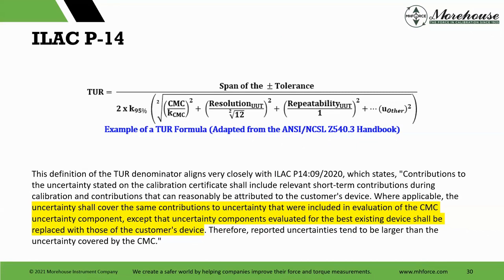So what we've done is we've simplified it down to, hey, we're making an assumption that people have done the CMCs correctly, and then we're saying, hey, what if we're going with ILAC? If we're accredited, we have to go with ILAC P14. So how do we make this formula work for ILAC P14? We say, okay, there it is. Uncertainty shall cover the same contributors that were included in the evaluation of CMC, except the uncertainty components evaluated for the best device shall be replaced with those of the customer's device. Therefore, reported uncertainties tend to be larger than uncertainties covered by the CMC. So we have to add.